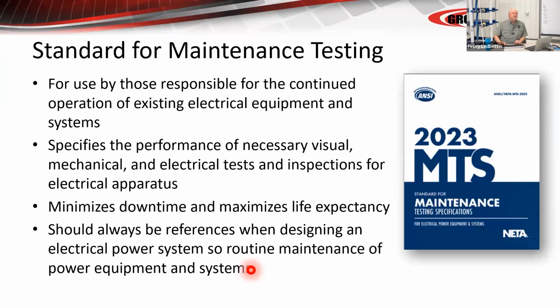The NETA maintenance standard is a great reference. You know, the Doble results from the Doble company years ago was a great way to look at oil testing and breaker testing. The MTS standard is a great way to get, I'm not sure about this, I want to check myself. It's a good idea to go compare to the maintenance standard, look at what should have been done, look at what results you should expect to get from the MTS. You don't have to be a NETA guy to conform to NETA standards.